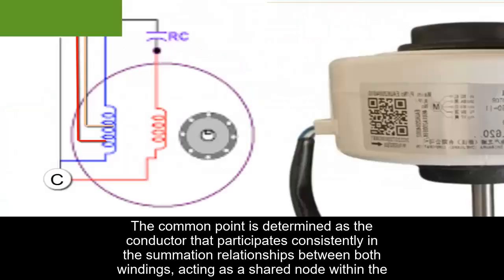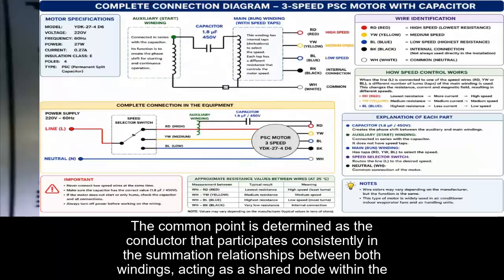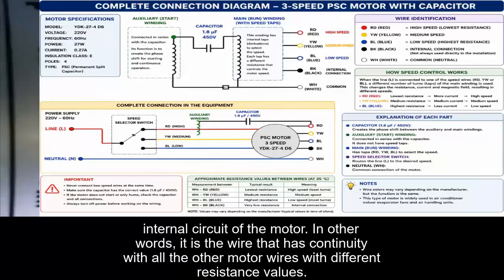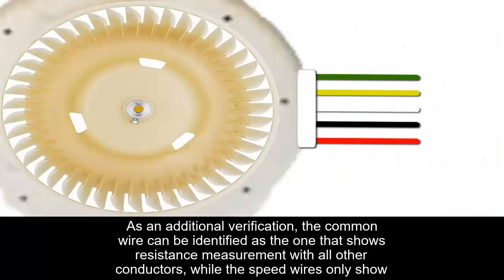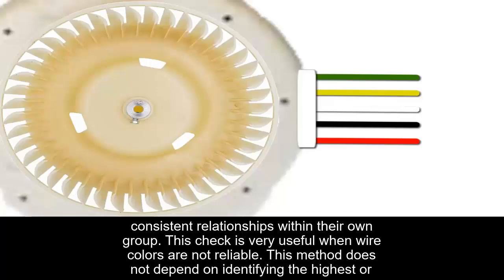The common point is determined as the conductor that participates consistently in the summation relationships between both windings, acting as a shared node within the internal circuit of the motor. In other words, it is the wire that has continuity with all the other motor wires with different resistance values, while the speed wires only show consistent relationships within their own group. This check is very useful when wire colors are not reliable. This method does not depend on identifying the highest or lowest resistance in isolation, but on the mathematical consistency between measurements, making it valid even in motors with multiple speeds or internal taps.